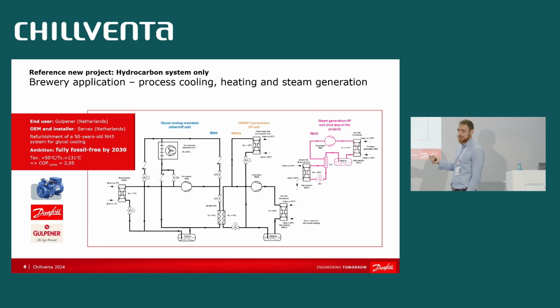So up to here, everything, as I said, is off-the-shelf product. Compressors, different technologies, components, it's there. And, well, it works. I was in the breweries. What is the next stage? This is generating 2-bar steam, where we use, again, a hydrocarbon, but it is butane this time, where the source is return water from processes at 60 C, and we evaporate at suction 50. For now, we have condensation of the butane at 131 degrees, where we heat up pressurized water up to 128 degrees. After this, we flush it down to 2 bars, and we get steam saturated at 2 bar, 122.24 degrees, if I'm correct.